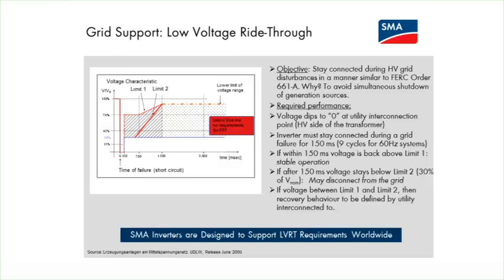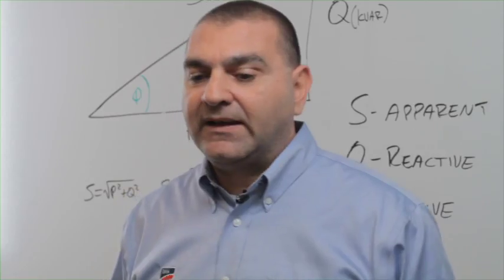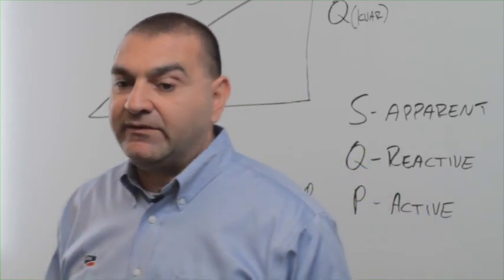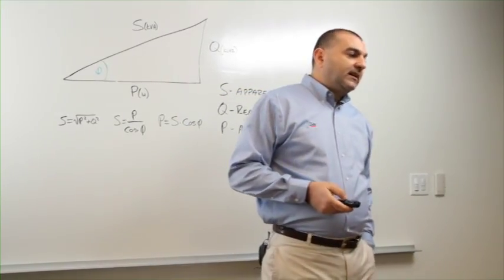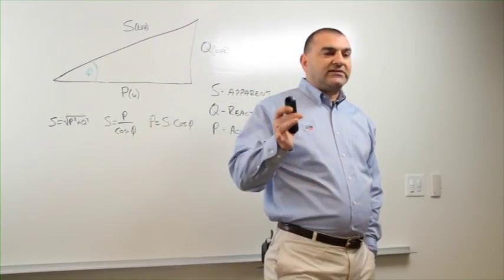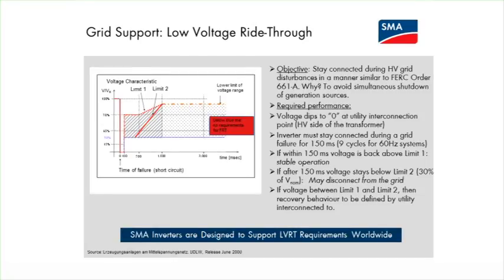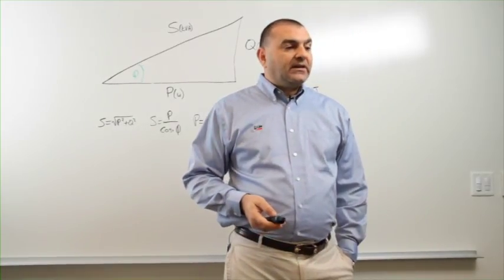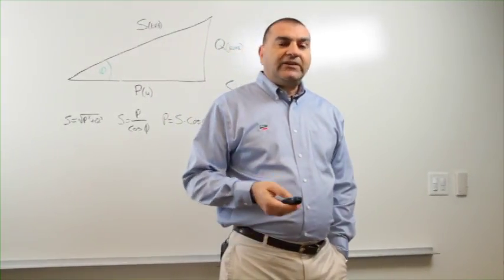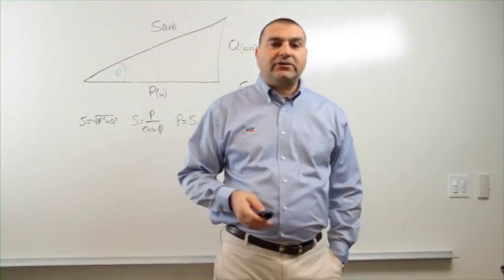Another important feature is the low voltage ride-through requirement from FERC Order 661-A that was imposed due to the high penetration of wind in the past. And now we're seeing more requirements coming also on PV. What happens here is basically the voltage dips to zero on the high voltage side of the high voltage transformer. In other words, the high voltage side of the grid dips all the way sometimes to zero. And the power plant is not supposed to disconnect, because if you do, then you are creating what we call a double contingency effect, a loss of a branch and a loss of a generation, which is a NERC violation standard, by the way. So our inverters are designed with the feature where you're able to ride through these voltage dips until the fault is cleared.